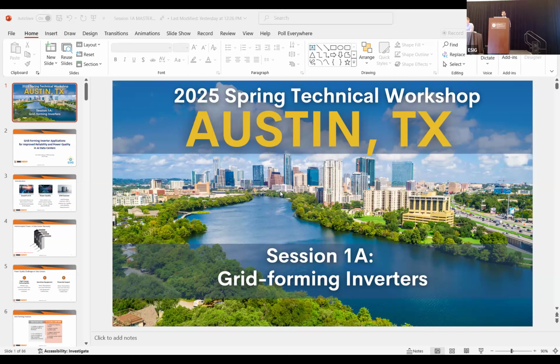So we decided, okay, let's find out the ability of an advanced grid support inverter to help out the system if it connects at the location marked in orange, close enough to the compensation, not at the same bus, not at the same POI as the wind plant, because this is a whole different OEM, a whole different developer coming in. They don't want to connect at the same POI. The type 3 wind resource does not want to become a hybrid plant. So that's out of the question.